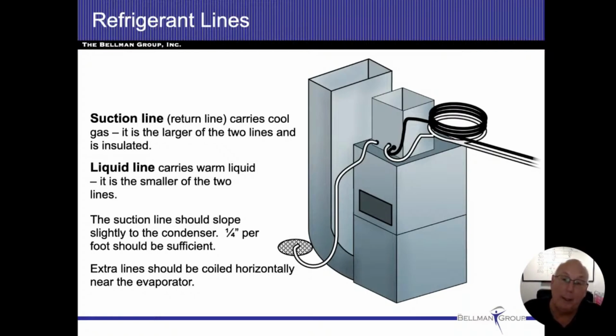But when you do it that way, you can't cut the refrigerant lines. So you're going to have to buy a line set that's longer than what you actually need. So there's always going to be extra line set. So what we don't want to do is have those coils that are showing on this screen going up and down. We want them sideways, as they're showing on here. If they're up and down, then the lubricant is going to be getting caught at the bottom of these, and it's not going to properly lubricate our motor. So again, it's an easy fix. Turn them horizontally. Don't leave them up and down.